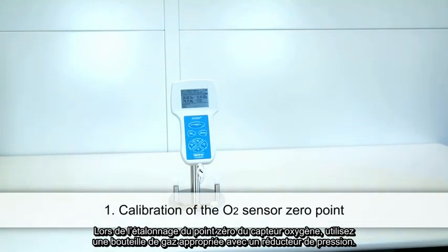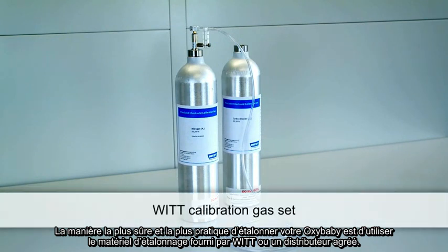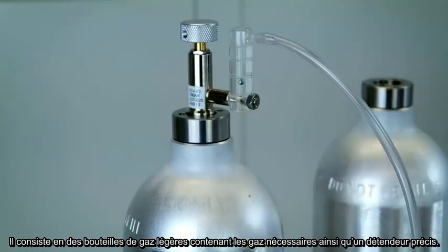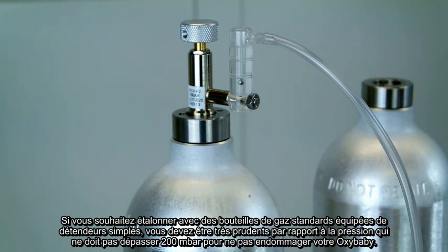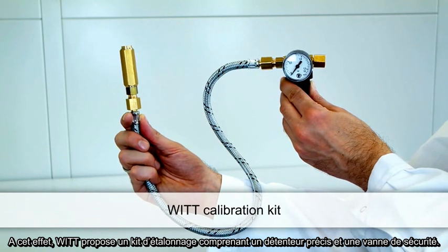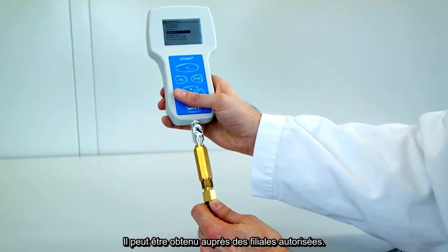When calibrating the zero point of the O2 sensor, use a suitable gas cylinder with a pressure reducing regulator. The most convenient and safest way to calibrate your OxyBaby is to use the appropriate calibration gas set by WITT or authorized subsidiaries. It consists of handy gas cylinders with the required calibration gases and a precision pressure regulator. If you prefer standard gas cylinders with simple pressure regulators, you must use a very low pressure — no higher than 200 millibar or 3 PSI — to protect your OxyBaby from damage. WITT also offers a calibration kit including a precision pressure regulator and safety valve, available through authorized subsidiaries.